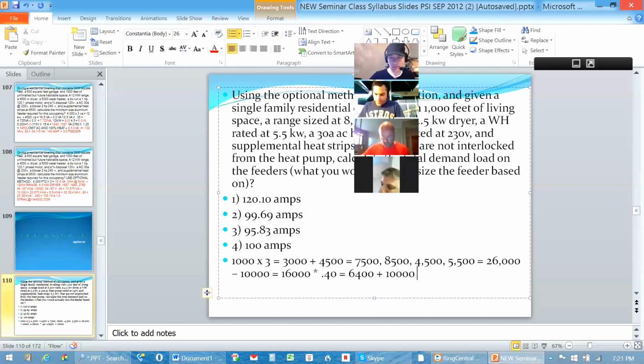Okay, where's the 10,000? If you look at the very heading of B, the instruction at the very top tells you that we're going to take the first 10,000 at 100%. So I have to subtract it, get it out of the way, apply my 40% against the balance, but I have to add it back in when it's all said and done.